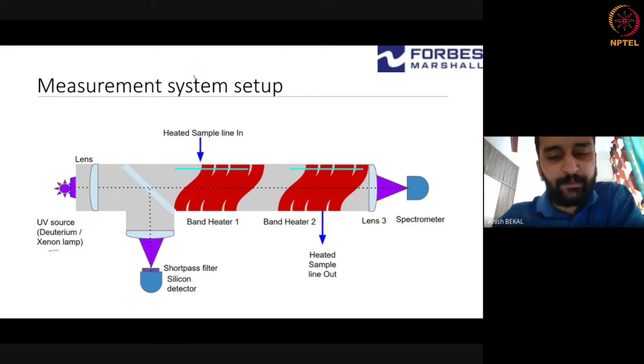Then you also take a reference using a silicon detector. So you get the spectra. You can always measure the concentration as a ratio of, for example, this is the SO2 spectra. You can always find the ratio of these two spectra, or you can use a polynomial fit method to basically fit a line across this region and then find different concentrations. Okay.